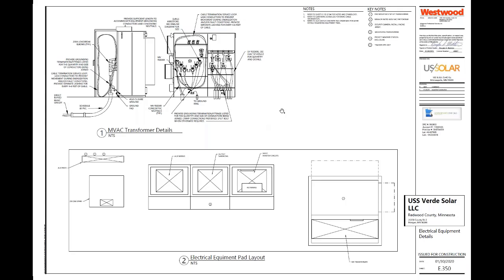What does that look like? This is also part of that same specification. In this case, they've done a little bit of a pad layout, and the engineer's proposing that medium voltage step-up transformer next to, they've gotten away from the cube design typically in these installations now, and it's more of a standard switchboard style construction. They're typically used to a flow either left to right or right to left, depending on the orientation of the site.